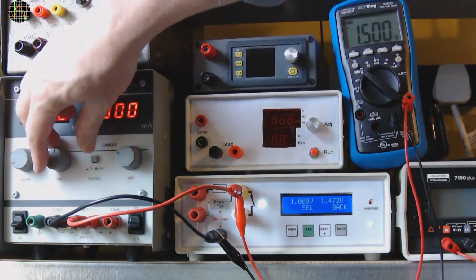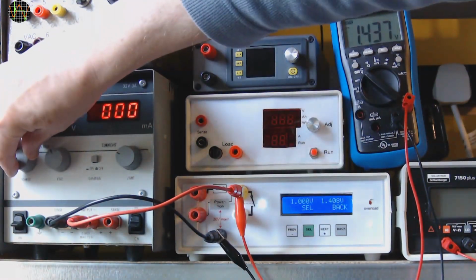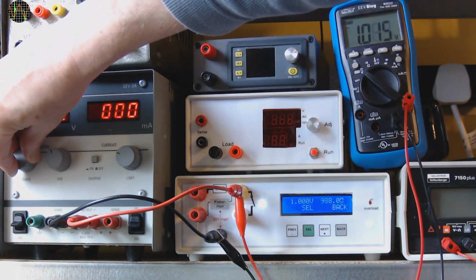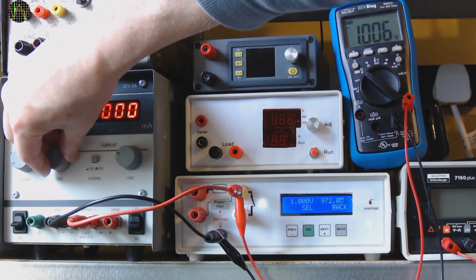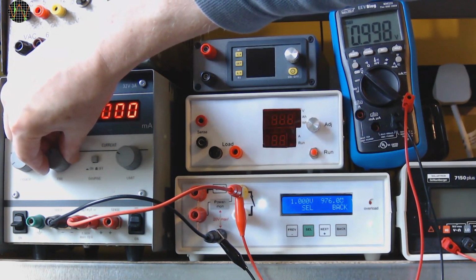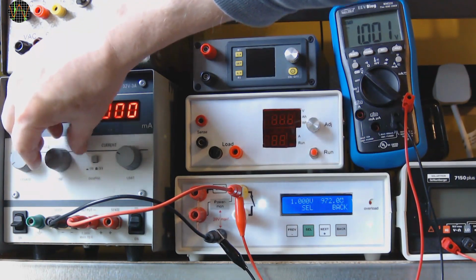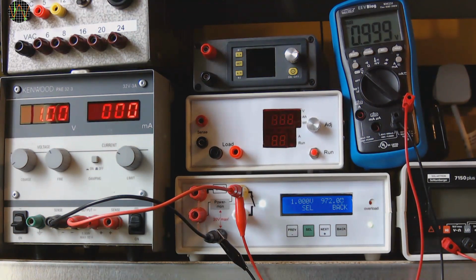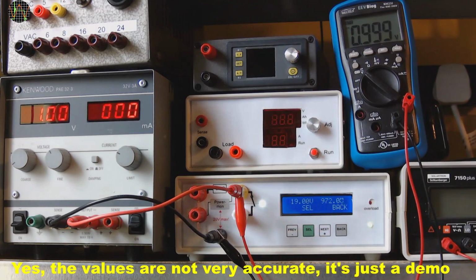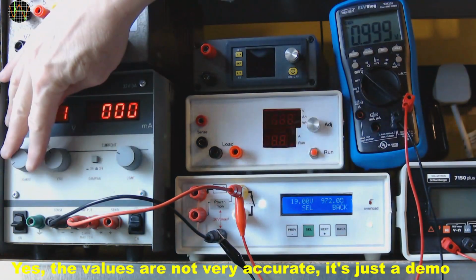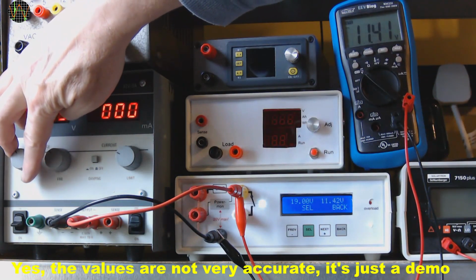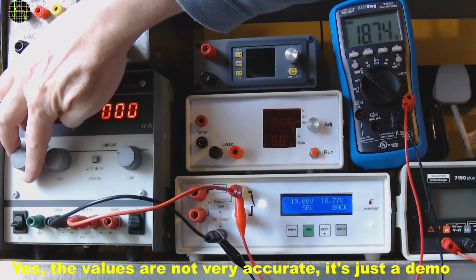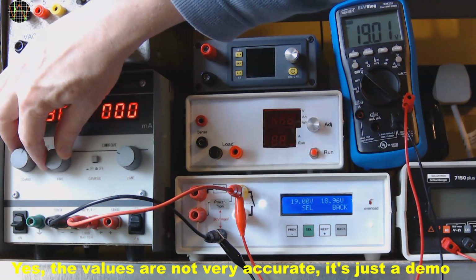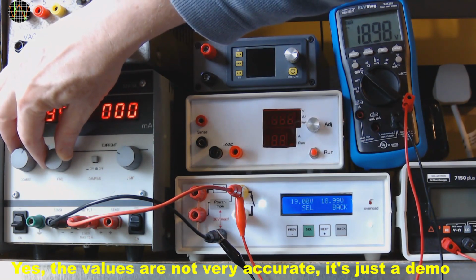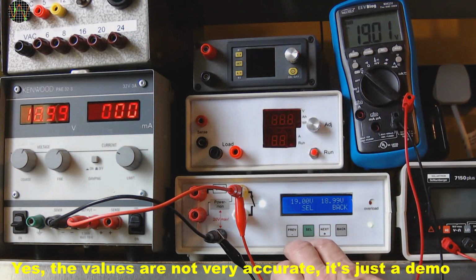You need now to adjust the voltage of your power supply until your reference instrument shows the target voltage. It is important, don't look at the actual readout of the LCD, this is just for control. You need to look at your reference meter when adjusting the voltage. It's a bit awkward trying not to block the camera when I'm doing this. Once you have it, press Cal and the program prompts you for the second target. I'm using 5% and 95% of the range as targets. Repeat the process in adjusting the voltage until your reference meter shows the target value. Press Cal again and the program calculates the calibration data, applies it and updates caldata.txt at the same time.